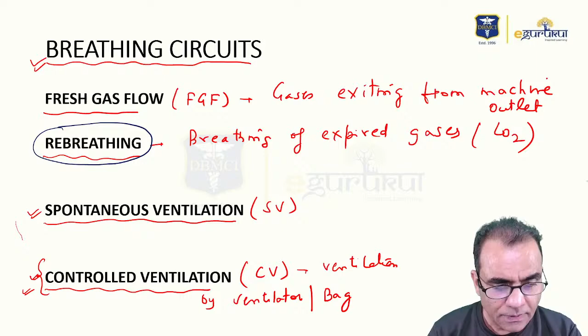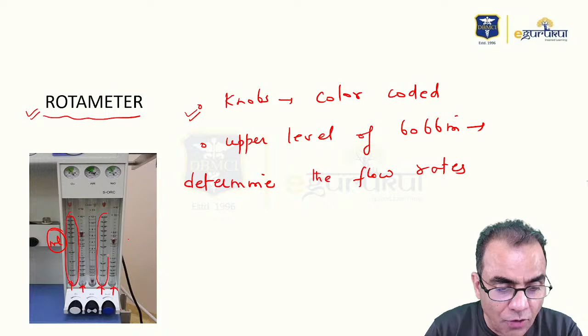Are you seeing two tubes? Some of you would have noted also. You can see there are two tubes for oxygen, two tubes for nitrous oxide. For air, it is still one tube. Why have they made two tubes? Because one tube is in milliliters and the second tube is in liters. What we are using in a circle system is 250 ml of oxygen, so that means we need a tube in ml. So this tube is in milliliters. Similarly, nitrous oxide, we are using 750 ml, so this is milliliters if you are using the circle system. That is why these modern day machines where we are using the circle system have two tubes, one indicating flow in milliliters, the second indicating in liters.